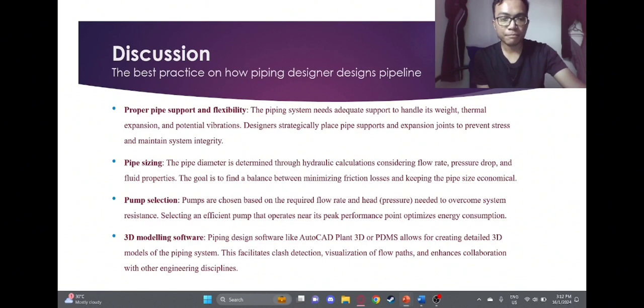The third is pump selection. Pumps are chosen based on the required flow rates and head pressure needed to overcome system resistance. Selecting an efficient pump that operates near its peak performance point optimizes energy consumption. And the last is 3D modeling software. Piping design software like AutoCAD Plant 3D, or PDMS allows for creating detailed 3D models of piping systems. This facilitates clash detection, visualization of flow paths, and enhances collaboration with other engineering disciplines.